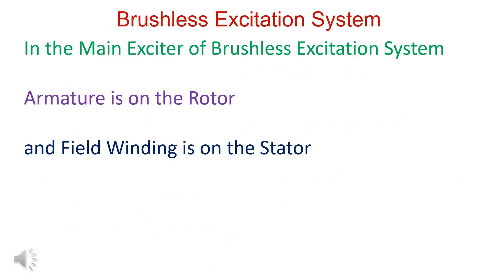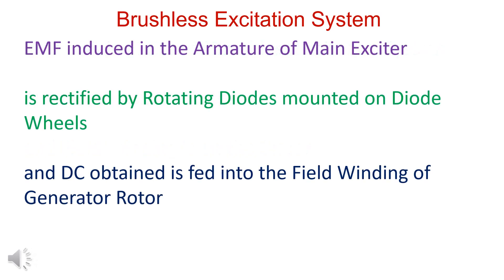In the main exciter of brushless excitation system, armature is on stator or rotor. Armature is on rotor. AC produced in armature is rectified by rotating diode bridge and DC current is fed into generator field winding.